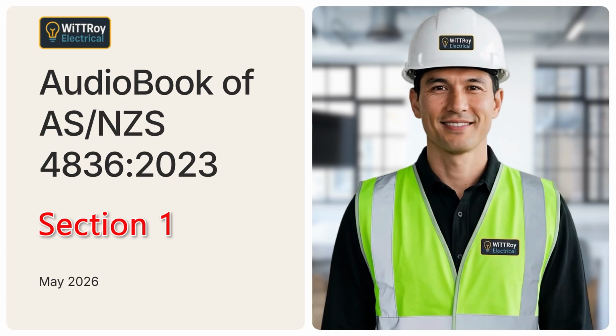Clause 1.4.6 Arc flash boundaries. Arc flash boundaries are the distances from energized equipment that should be maintained to manage the arc flash risk. In simple terms, the closer a person is to the possible arc source, the higher the risk. These boundaries help workers decide where people may stand, who should be kept away, and what PPE may be needed.